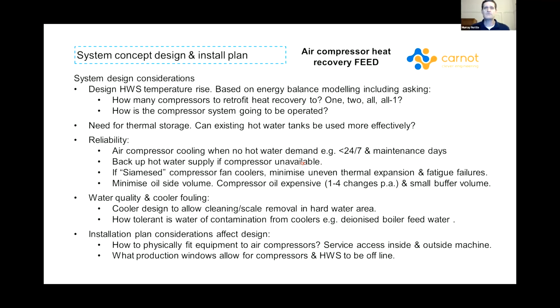Similarly, what happens if one of your air compressors is down for servicing? Say you've only fitted heat recovery to one of the compressors. When it's getting serviced 3 or 4 times a year, as they will, what happens with your heat supply system then? So you do have to have an alternate source of hot water for that backup scenario.